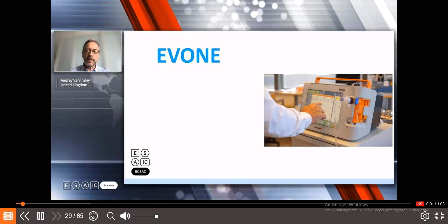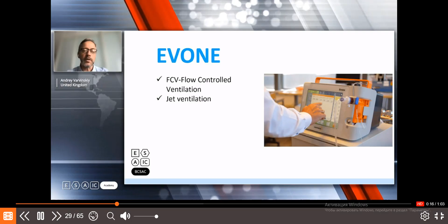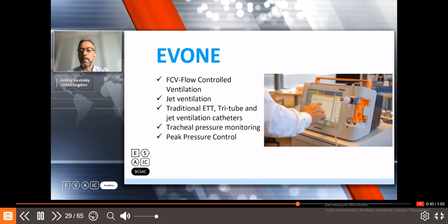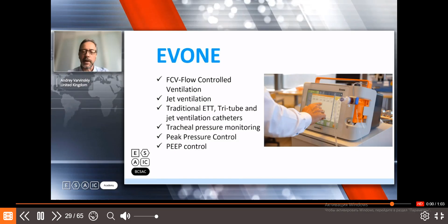Evone is the automatic version of the Ventrain, using this new and unique mode of flow control ventilation, and jet ventilation as well. If you're using the tri-tube that comes with it, you can use a conventional tube, not just the tri-tube. You can use other jet ventilation catheters, different types of tubes. But if you're using the tri-tube with the cuff, then you will use the flow control type ventilation mode, where again you provide active inspiration and active expiration. The machine will monitor tracheal pressure, peak pressure control, PEEP control, and also, as you can see here, there is this little device, the mainstream capnography. So you will have a normal capnographic line like with any conventional ventilator.